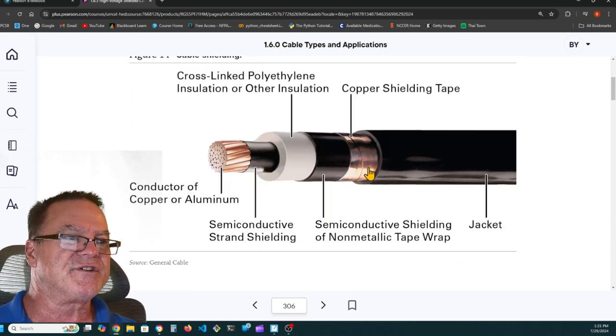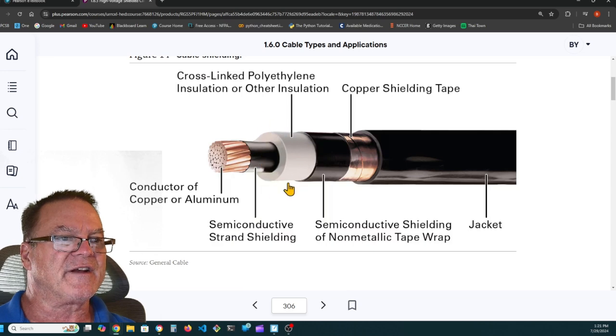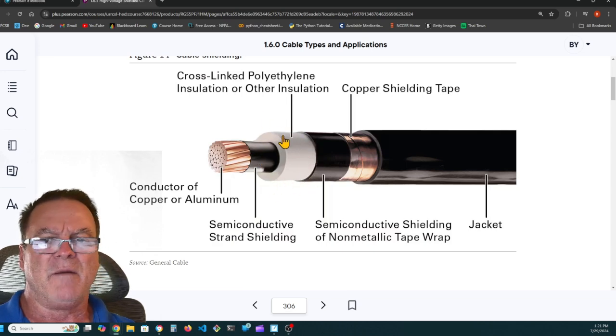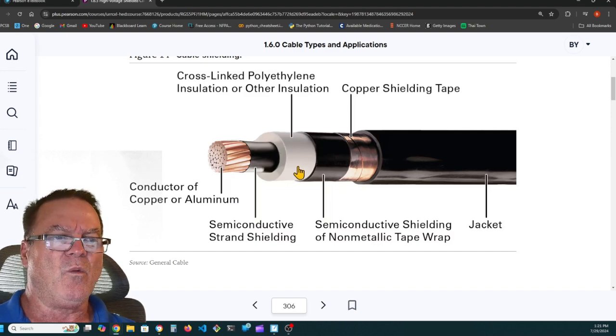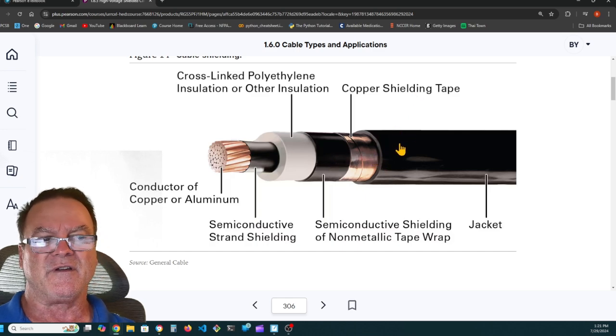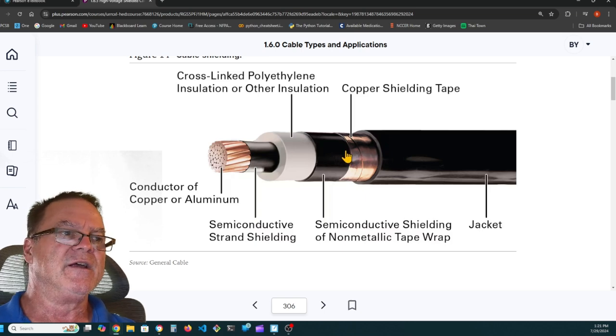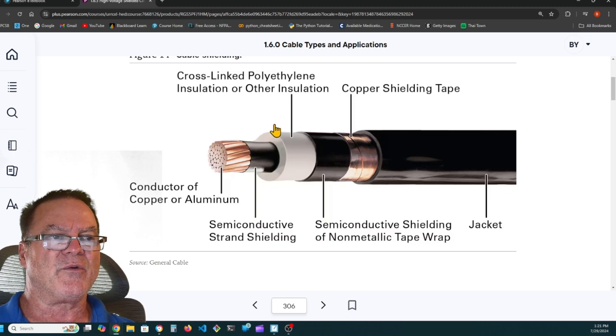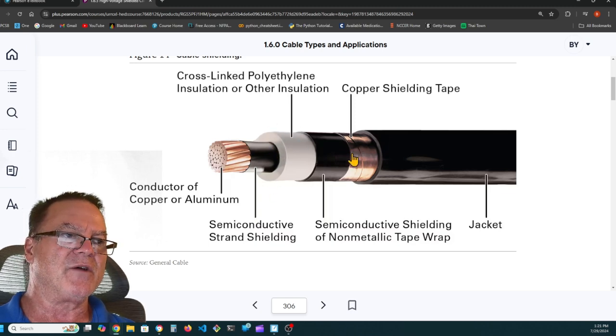So at these higher voltages, there's a corona effect that's going to build up a static charge, much like a capacitor. And we don't want that to happen because it can get to where it'll damage the insulation. It'll blow a hole through the insulation of the wire, and then the wire will be no good. So we take that buildup, that corona static layer, and we take it to ground with this copper shielding tape. There's a semiconductor shielding of non-metallic tape wrap. Then there's the cross-linked polyethylene insulation or other insulation. And then finally one last semiconductive strand shielding. And here's your conductor of copper or aluminum.